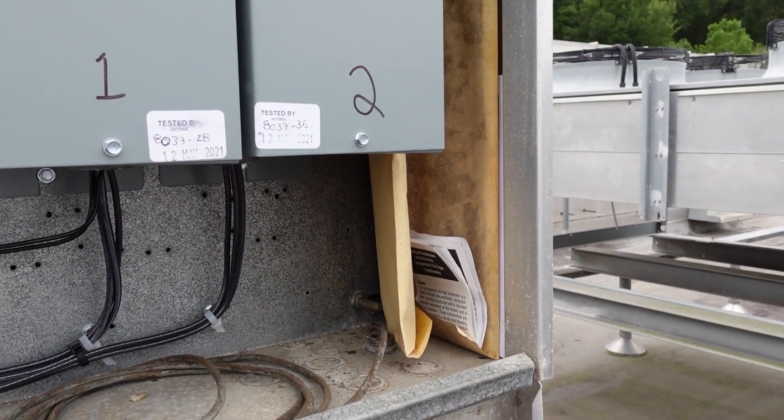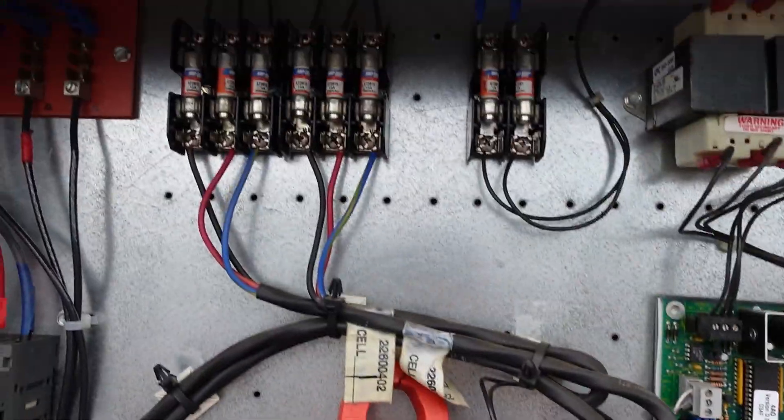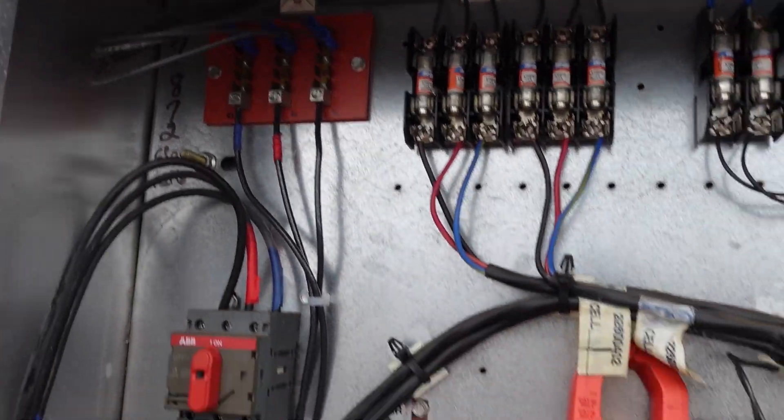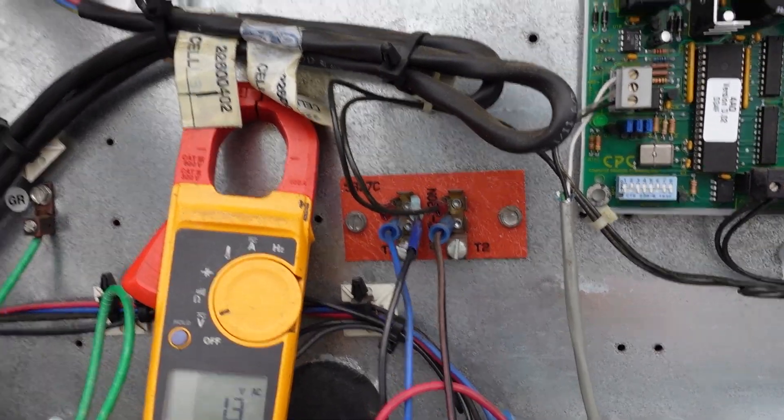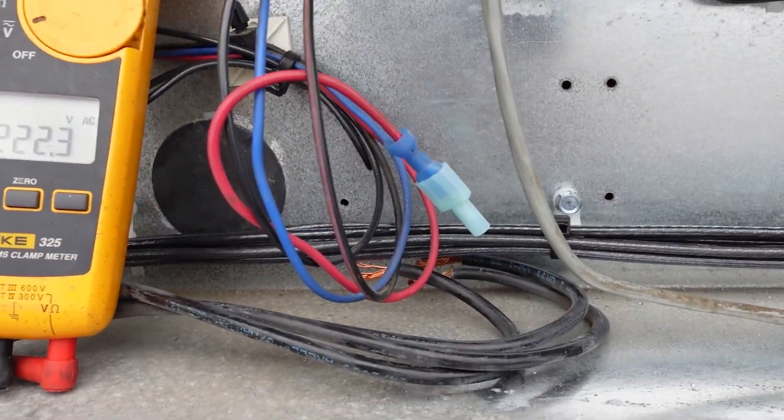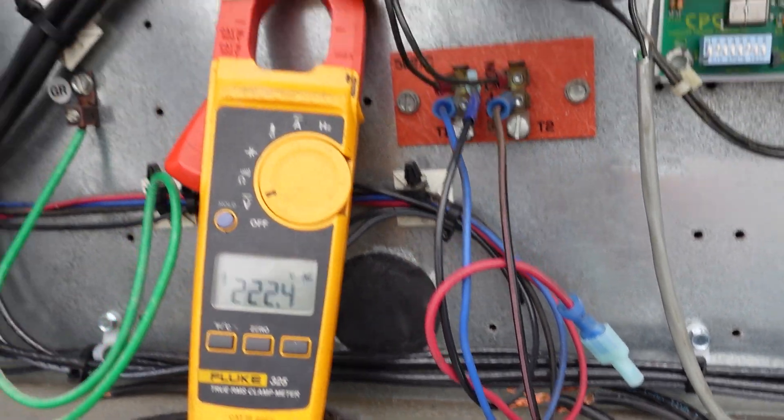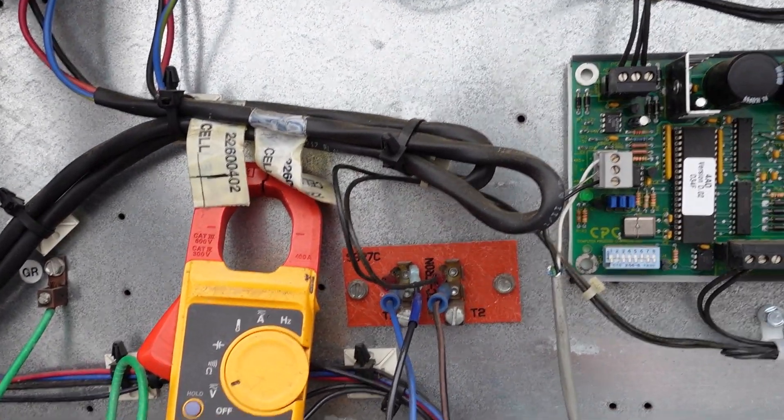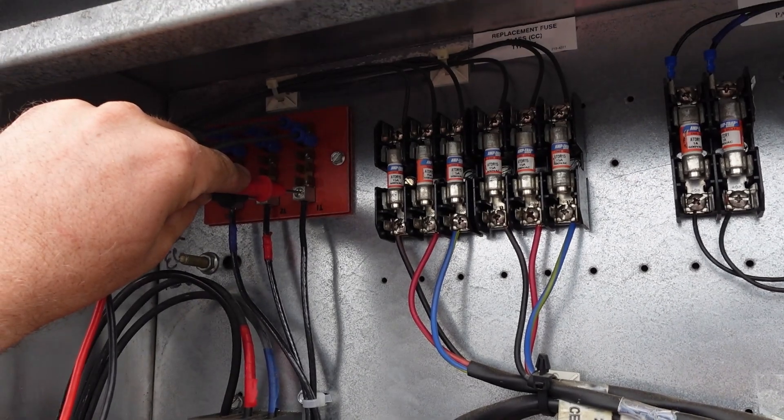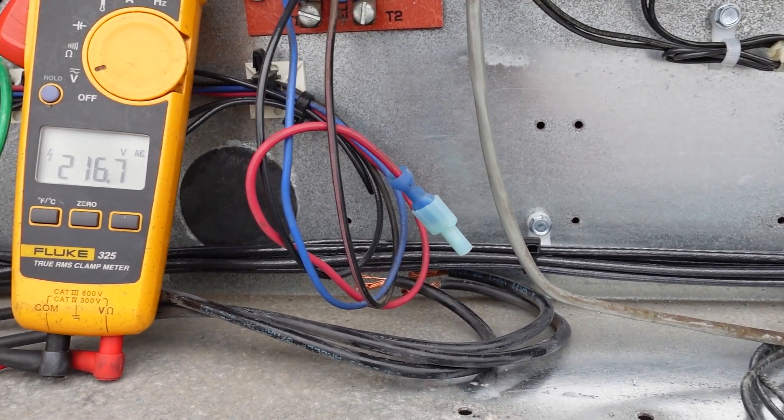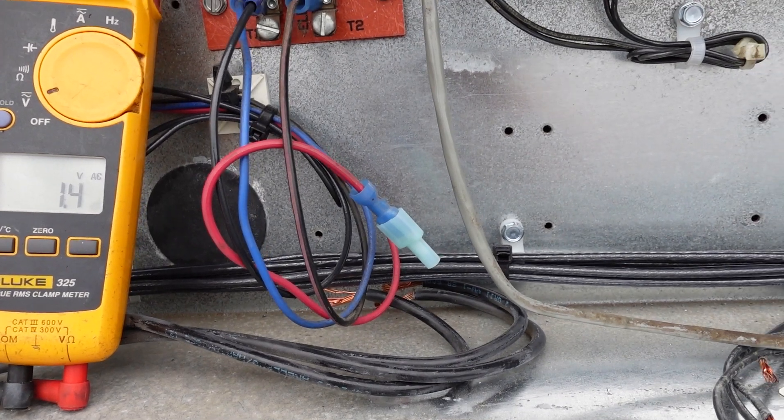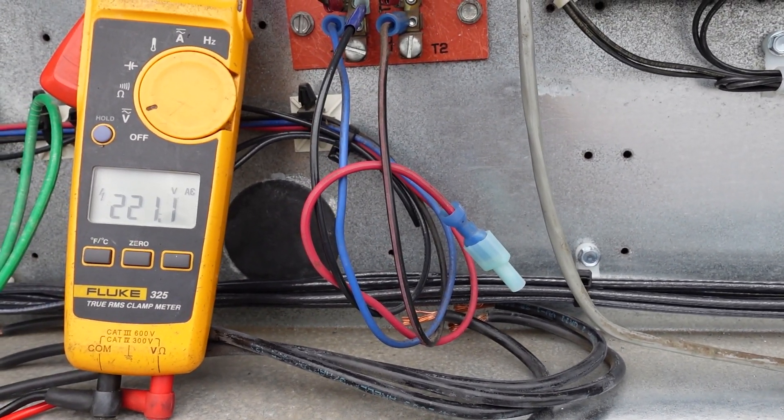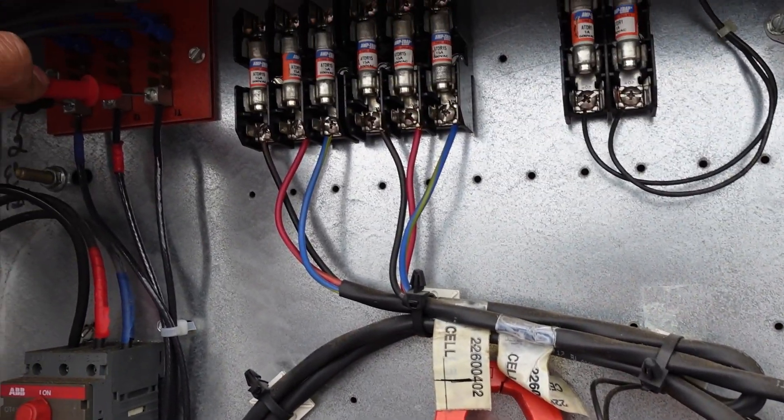That goes into our transformers and it comes out on our terminal board top left. So now if you look at the meter again, we're going to do one to two up there. You can see we have 222 volts. Two to three, 217, 221 from one to three.